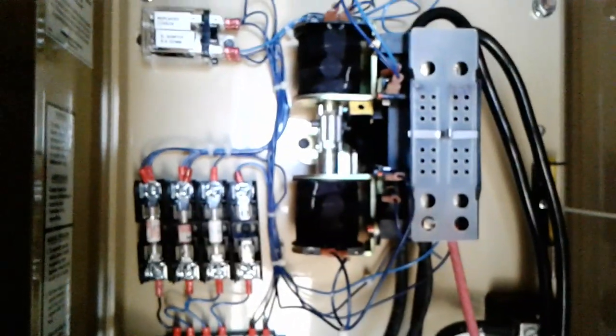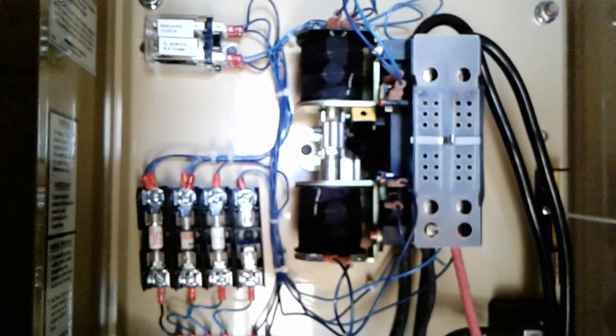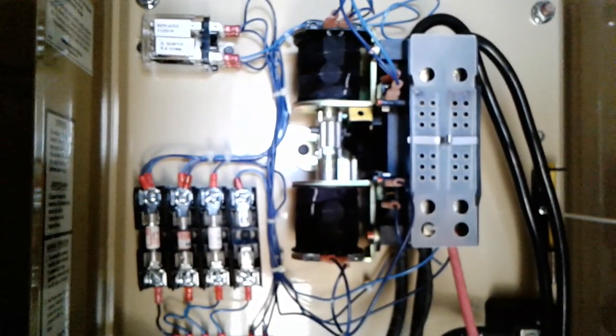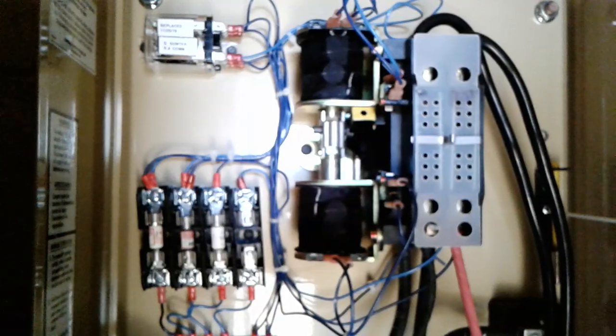Okay, and then it has another delay while it comes up to speed, and then this transfer switch right here should throw automatically. Okay, we're on backup power.